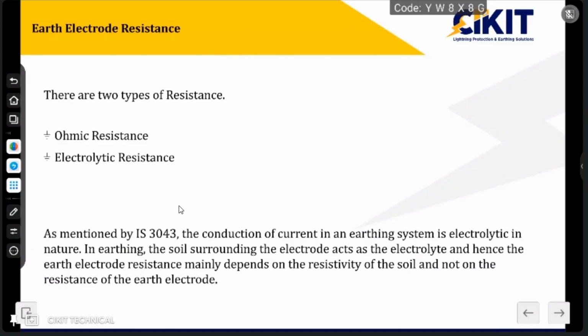So many people will be having an idea that if a system is working well, then the earthing resistance value should be less than 5 ohms. Or in some cases they will tell that if the resistance value is less than 1 ohm, then the system will be considered a good system. But that is not the case. So the resistance which we are explaining is generally the electrolytic resistance.